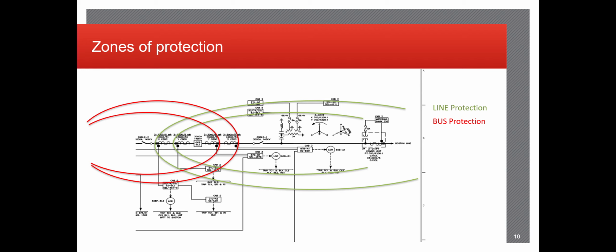And you can see where the overlap occurs for both sides of the protection. The bus protection actually goes to the right side of the breaker, and the line actually goes to the left. This is done so that you're covering as much of the zone as possible, and you can also see that the primary and backup will be overlapping on the CTs on the left and the right there.